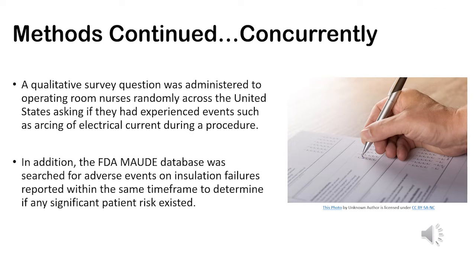To continue with the methods, a qualitative survey question was administered to operating room nurses randomly across the United States, asking if they had experienced any such events of arcing of electrical current during a procedure. In addition, the FDA MAUDE reporting data system was searched for adverse events on insulation failures reported within the same time frame of the study to determine if there was any significant patient risk that existed.